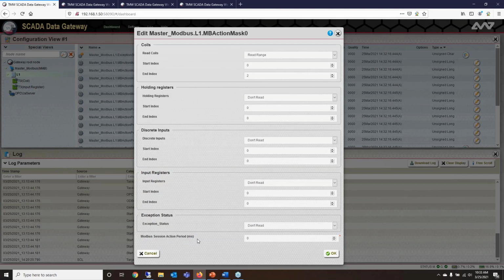Generally, with polling, you're gathering a large set of data, even if it is the data that you already have within your database, and that can take up a lot of bandwidth. So generally, your polling rates are going to be kind of slow. I've seen them as much as once an hour type thing, where it reads everything once an hour, and it relies on other data methods in order to get data more quickly, but use up less bandwidth. For this demo, because I don't want to sit around for an hour waiting for this, I'm just going to set it to 15 seconds and then hit OK.